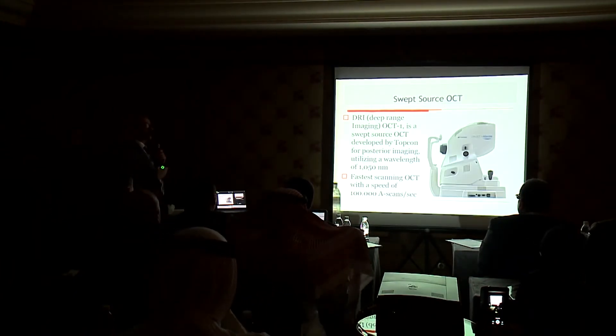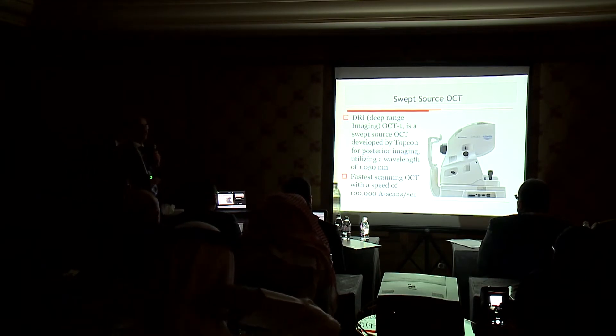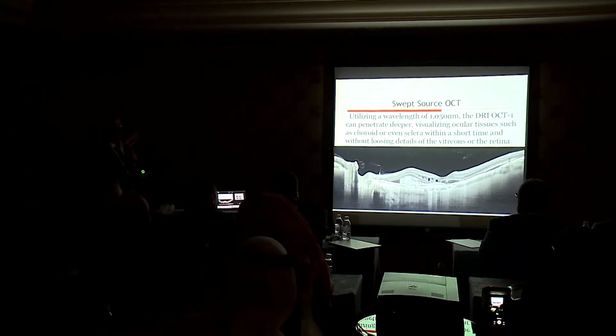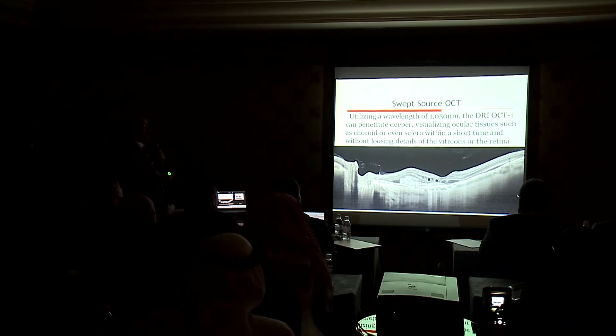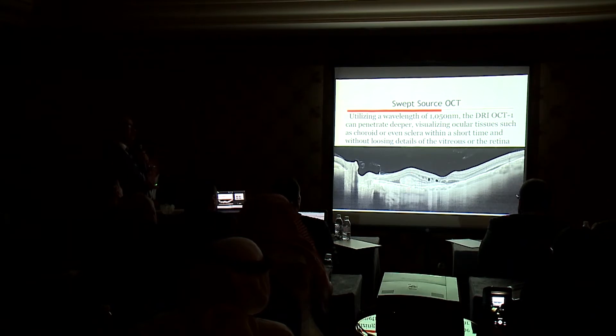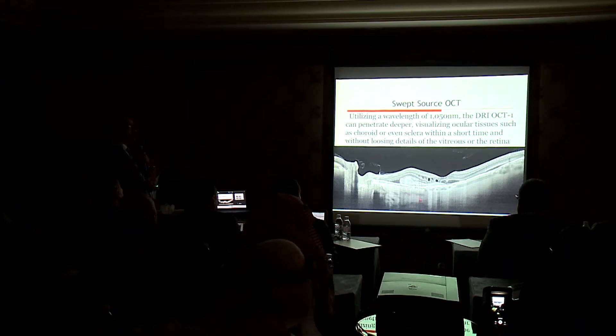Then came the swept source with deeper penetration, longer wavelength, and most importantly the fastest scanning OCT — about 100,000 A-scans per second — so it can sometimes overcome saccadic movement and artifacts in the pictures. This is a picture of swept source OCT where we can see the vitreous clearly, the vitreous separation at the disc, and the retinal layers very clearly. We can see the lesion without shadowing below the region, so we can clearly see the choroid up to the sclera.